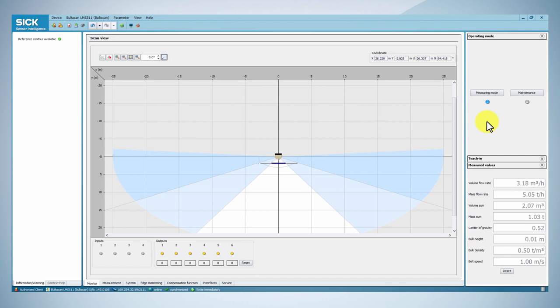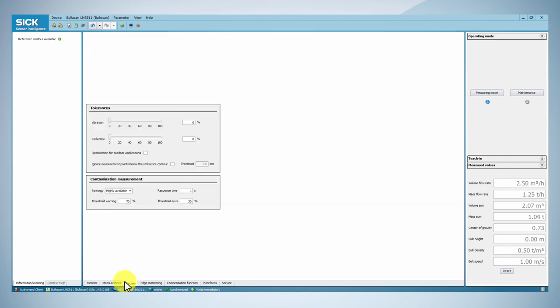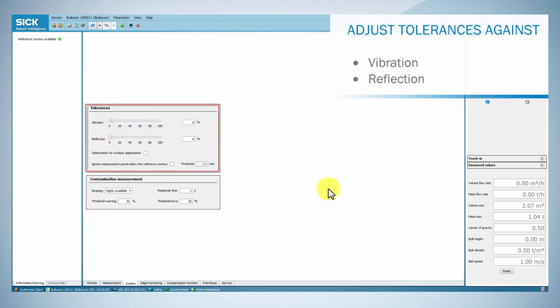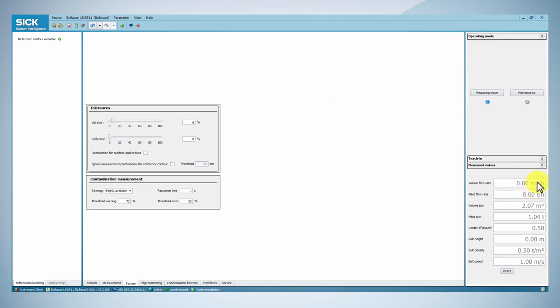In order to optimize measurement performance, you can set up the system parameters. Under the system tab, you can adjust the tolerances against vibration and reflection. Reduce or increase the tolerance against vibration so that the volume flow rate measured value remains constant at zero, with an empty conveyor belt.